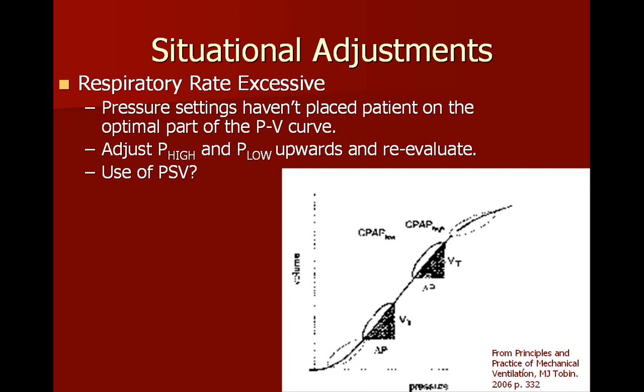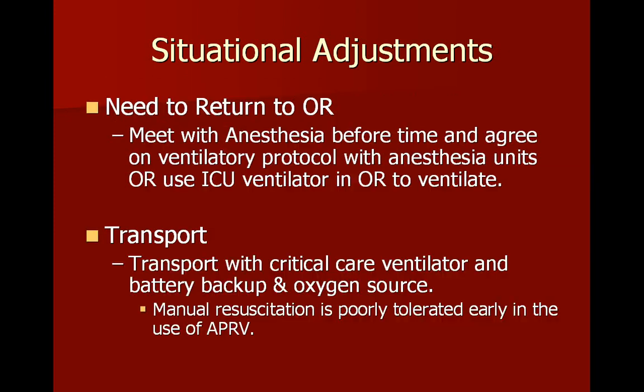Plus, how you set pressure support is really a trick, because pressure support, at least on the 840, is referenced to the P low. I've seen people who have a P low of 5, a P high of 20, and they put 10 of pressure support on. It doesn't do anything, because until the sum of the P low and the pressure support gets above 20, it's not delivering any pressure support. So, it's kind of an FYI. But push them up the curve.